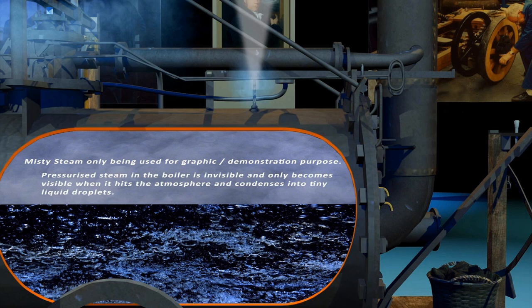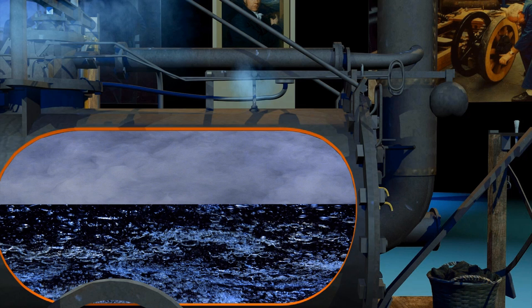But strange things begin to happen when we place the cannonball weight on the end of the arm lever. At its furthest extent of the lever arm, our 42 pound weight now exerts a downward force of about 105 pounds on the safety valve. Now, this value reduces back down to 42 pounds as we move the weight closer to the valve itself. So, by positioning the weight between these two points, we could vary the force being applied to the valve from between 42 pounds to 105 pounds.